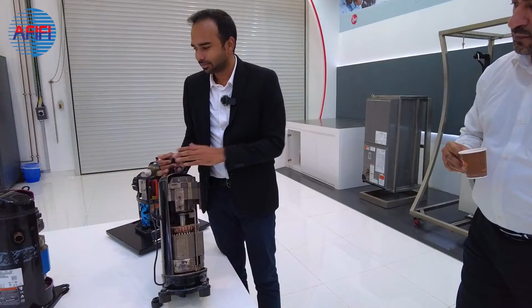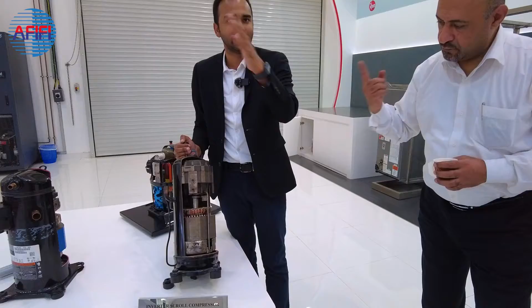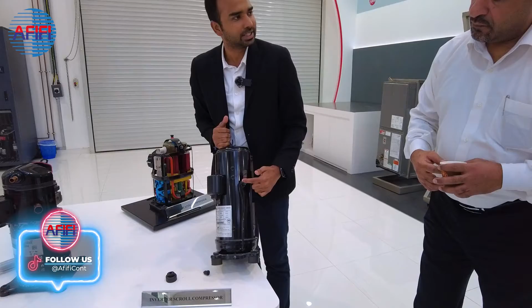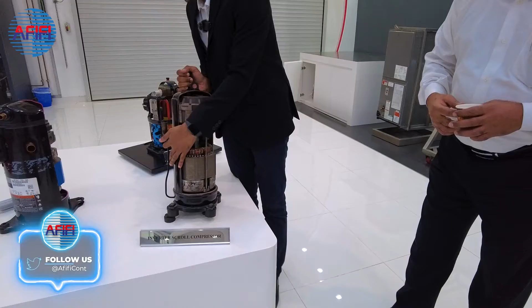Now a typical compressor is like this, a fixed speed compressor. Additionally, you'll see these oil return lines. This is basically an oil return line from the high to low side. Since VRF can go to really long pipe lengths, most of the oil will be recovered here, and also some will be recovered here as well. So we don't have to worry about the length of the pipe. There are more oil return lines, so that's how VRF units actually go to these really long pipelines. Because you are not losing your oil into the refrigerant pipes. You are reclaiming it immediately within the compressor. So 85% of that oil is reclaimed within that circuit itself.